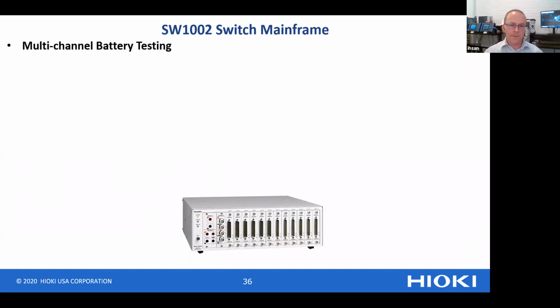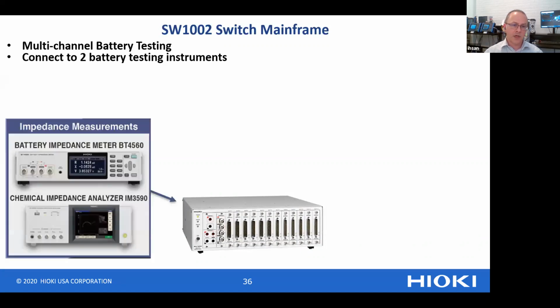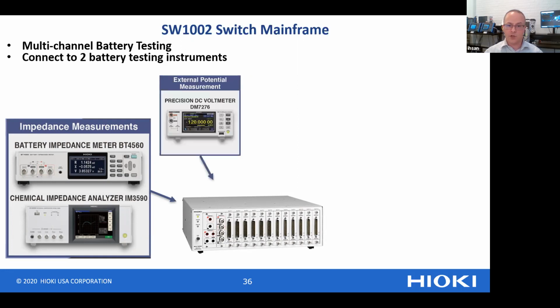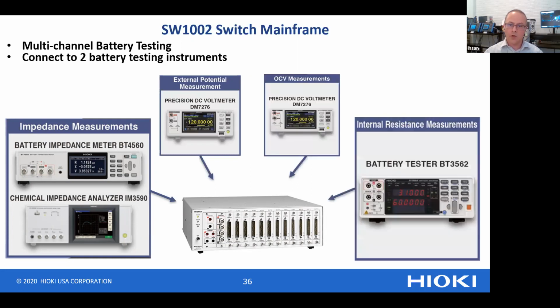You can have up to 2 different battery testing instruments connected to this. For instance, you could have the chemical impedance analyzer or the battery impedance meter for impedance measurements or sweeping. Or if you're just doing voltage measurements, you can connect a single voltmeter. Or you can also connect the battery tester, the BT3562. So it's capable of connection to more than one instrument, depending on your test flow.